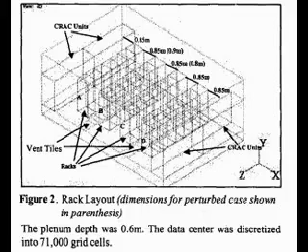From the figure, the racks are laid out in rows separated with hot and cold aisles, as shown in the figure. While the cold aisles supply cold air to the system, hot aisles are designed to remove hot air from the system. Although racks come in standard size, improper layout can radically change the fluid mechanics inside the data center, leading to inefficient operation of CRAC units.